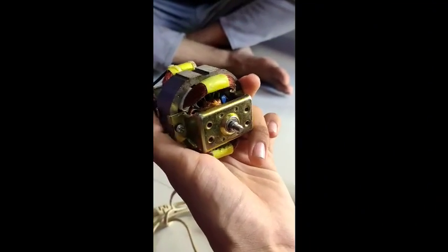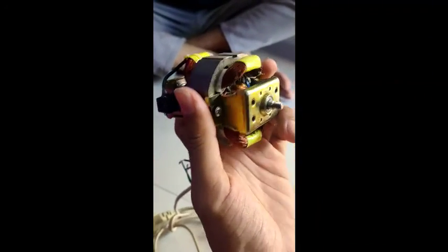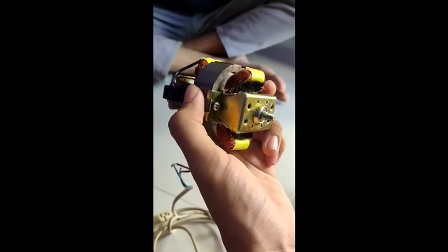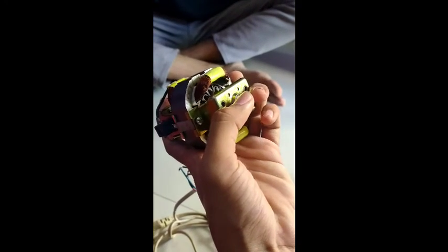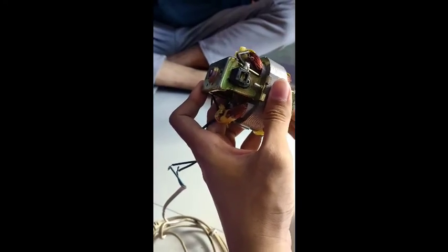What are the components of an electric motor and their functions? The first is the stator. The stator is a major component of the electric motor because it directly affects motor performance. The stator is a static copper winding and is usually located surrounding a main shaft. The function of this stator is to generate a magnetic field around the motor.